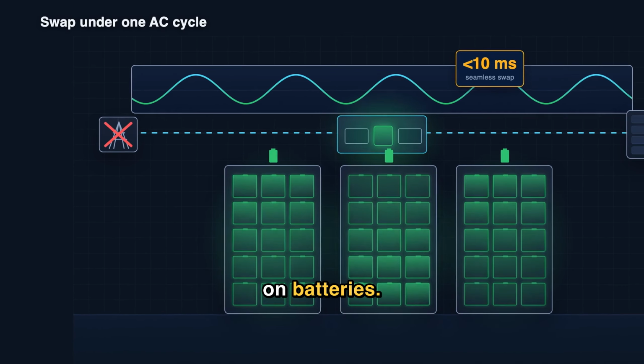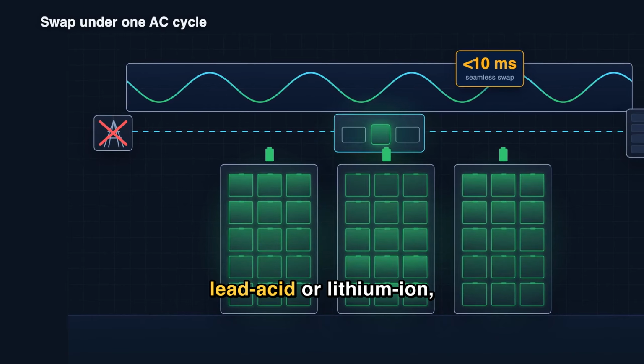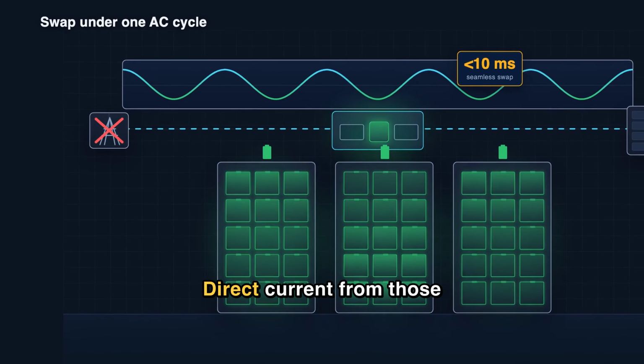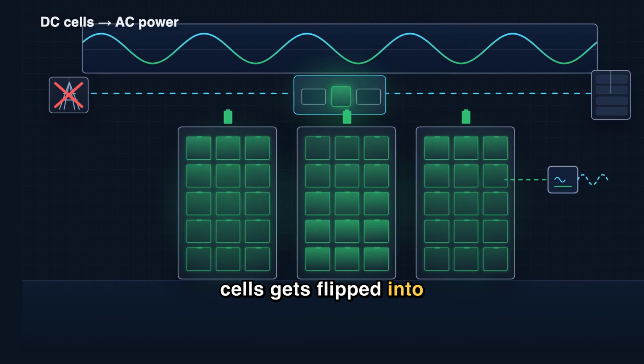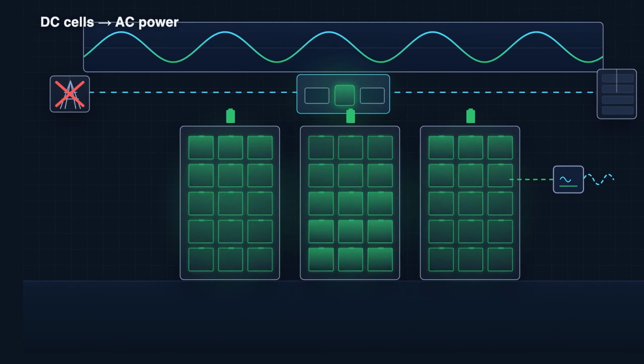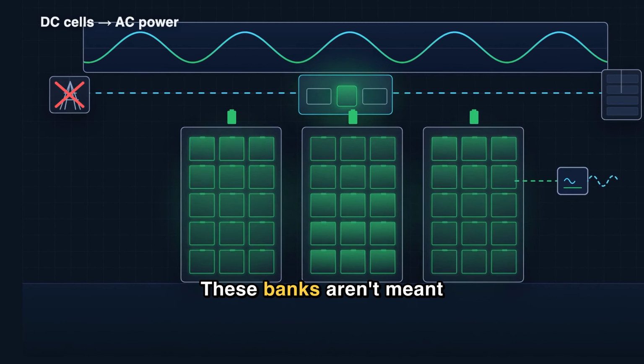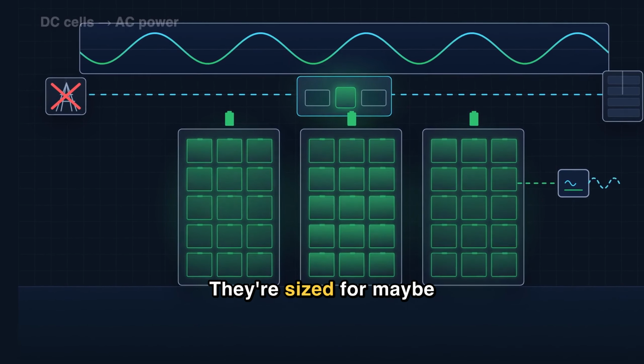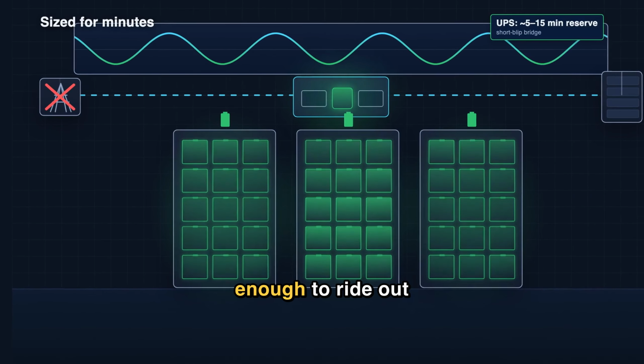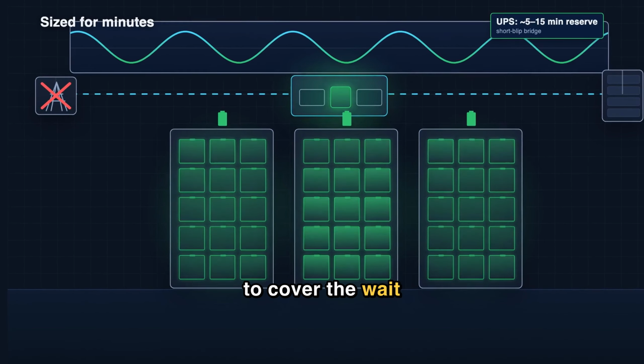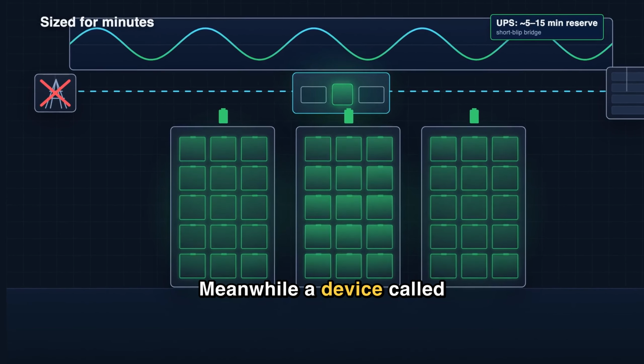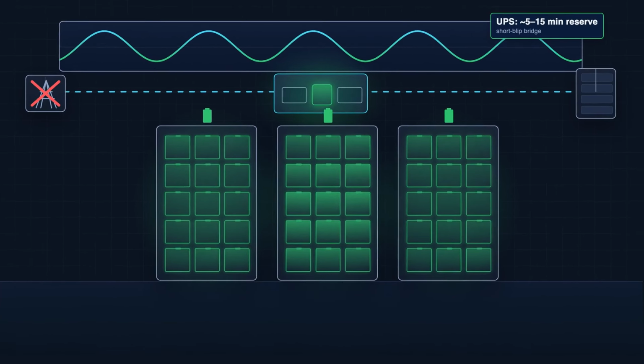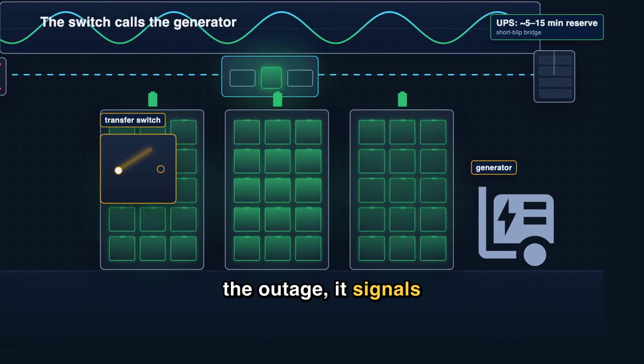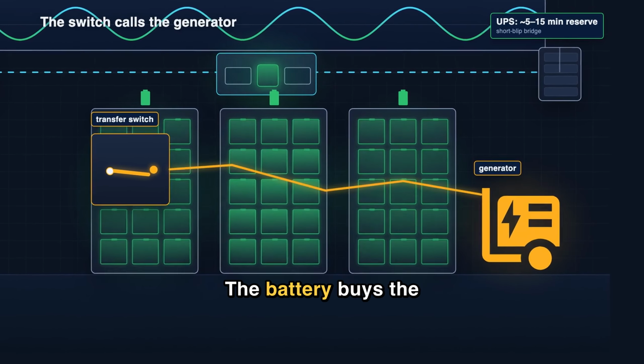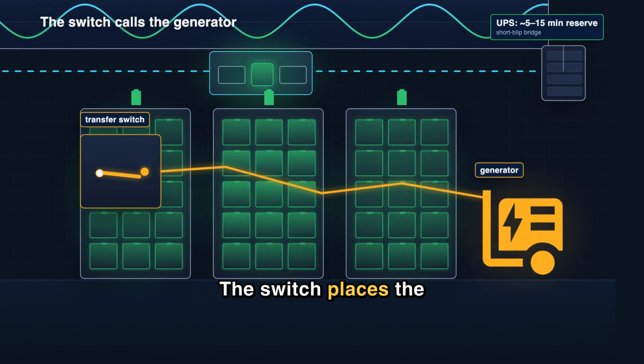Most of these run on batteries. Picture rows of cells, lead-acid or lithium-ion, stacked in cabinets. Direct current from those cells gets flipped into the alternating current servers need. Now here's the design choice. These banks aren't meant to run for hours. They're sized for maybe 5 to 15 minutes, enough to ride out a short blip, or to cover the wait while the generator starts. Meanwhile, a device called the transfer switch is watching. The instant it sees the outage, it signals the generator to fire up. The battery buys the time. The switch places the call.